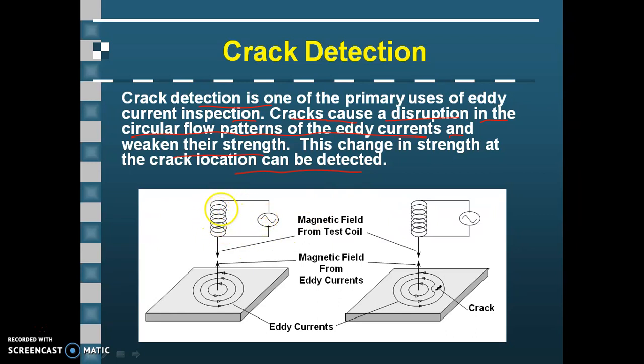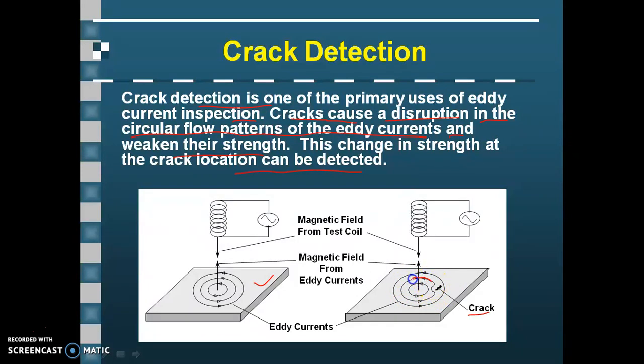Here the coil is present and we have applied the AC current source across the two probes of the coil. Eddy current will generate in the metallic sheet which is close to the coil. The eddy current produced in a crack-free or no-defect sheet is purely circular, so the electromagnetic field produced by the circular eddy current will be much stronger. But for a sheet where cracks are present, some defects are there, and due to these defects the eddy current pattern is not purely circular — it is distorted in shape.